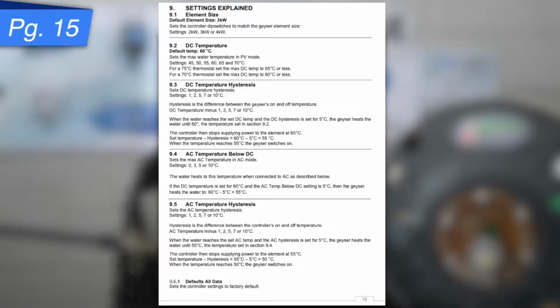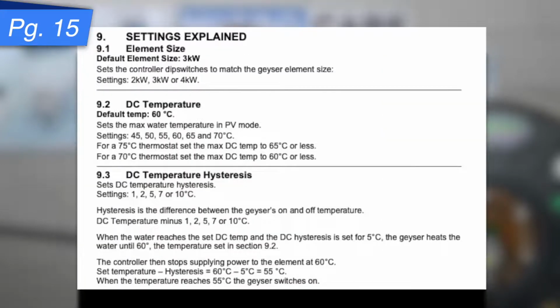Right, we're going to move across to page 15, and now we're getting ready to switch on the units. Now, just in terms of the settings, the Microcare Geyser Controller comes with default settings. The default size for the element on page 15, 9.1, is a 3 kilowatt element. Now, if you don't have a 3 kilowatt element, you're going to need to make a change.